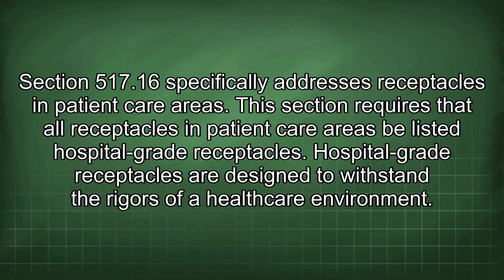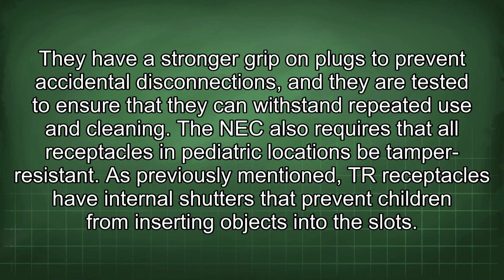This section requires that all receptacles in patient care areas be listed hospital-grade receptacles. Hospital-grade receptacles are designed to withstand the rigors of a healthcare environment. They have a stronger grip on plugs to prevent accidental disconnections, and they are tested to ensure that they can withstand repeated use and cleaning.